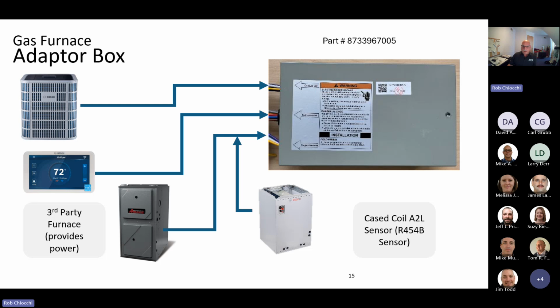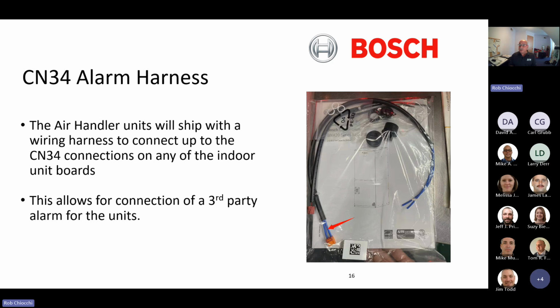One more thing incorporated with the Bosch air handlers will be this packet. This packet includes a wiring harness that will connect from the circuit board in the Bosch air handler to a third-party alarm system. Across the country, we're getting more and more reports of municipalities and states requiring the A2L leak detection mitigation system be hooked up to a third-party alarm system. We haven't experienced that much yet in our APR footprint, but Bosch is going to include this wire harness with their air handlers, so it doesn't have to be a spare part that needs to be provided. I just wanted to make you aware of this, so if customers ask what this is for, you now know. It's to incorporate the A2L leak detection system into a third-party alarm system if need be.